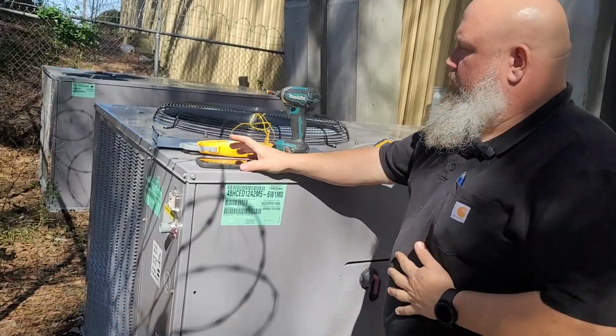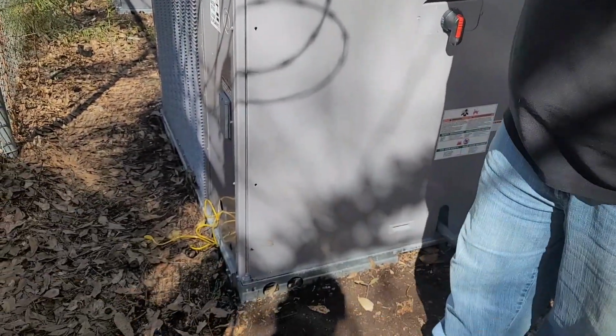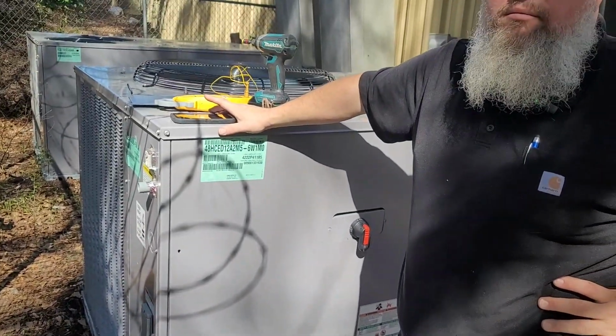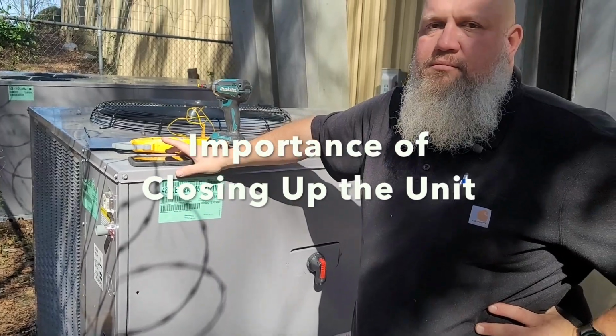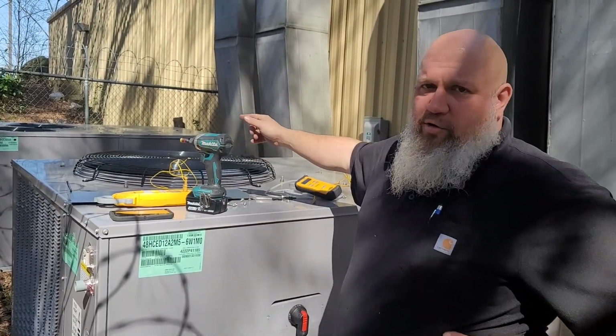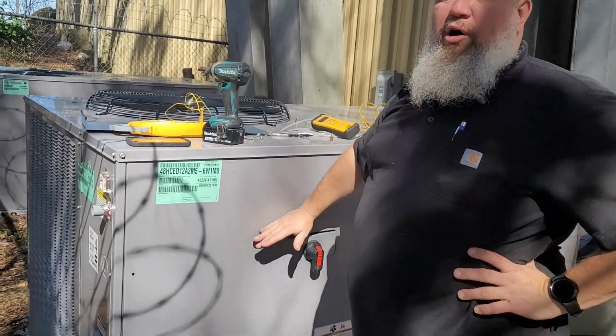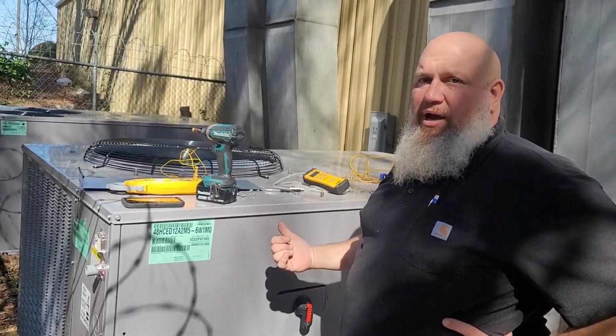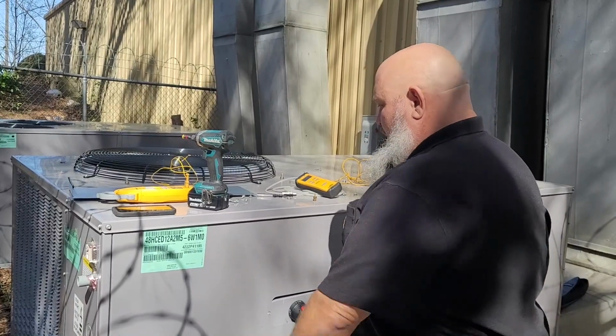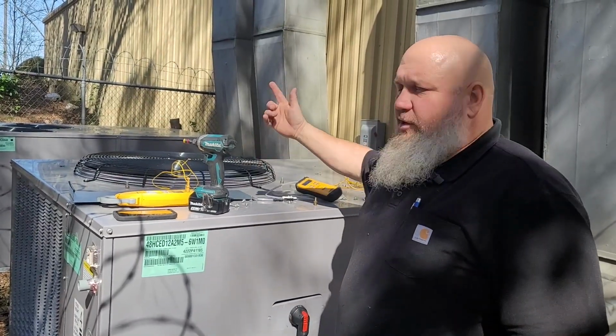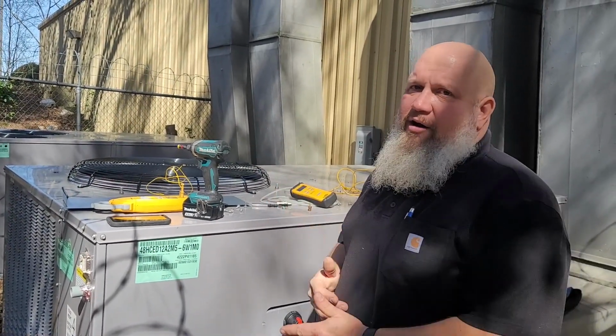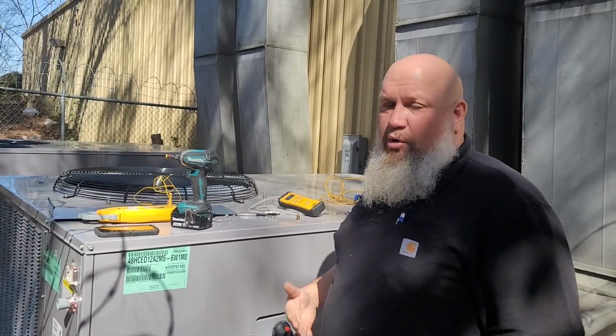Why did you put the temperature probes on, run them out that hole, and then put the panel back on? What does that do for you? This fan is pulling the air through the coil. If you have this door open, air is going to follow the path of least resistance, and all the air is going to come through here, and that coil is just going to get hotter and hotter because you're not pulling the air through the coil.